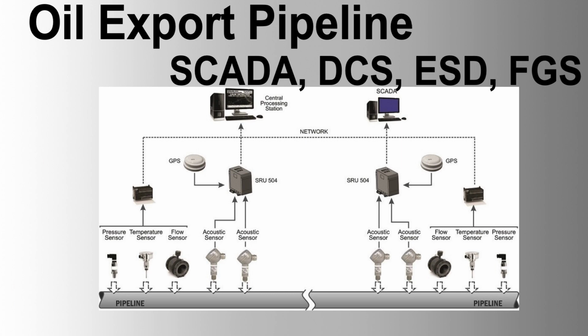Distributed Control System, DCS. Function: process control and monitoring at various pipeline sections and stations. Design aspects, integration: combines process control and monitoring functions into a single system. Hierarchy: segregated into Safety Network, Process Control Network, PCN, and Supervisory Control Network, SCN. Controllers: distributed controllers tied into a process control network via a fiber optic backbone. HMI: human-machine interface for process control, shutdown operations, and alarm management. Advanced applications: compensation and correction functions, sequence control, and logic functions.